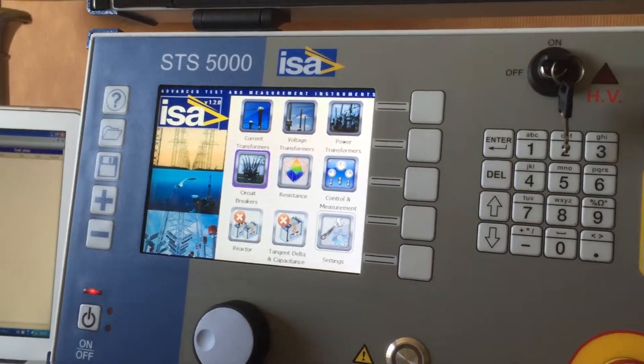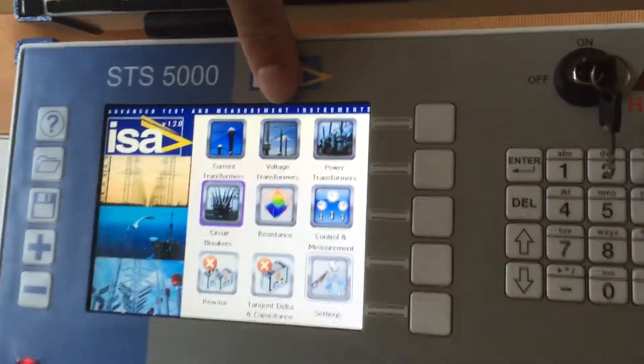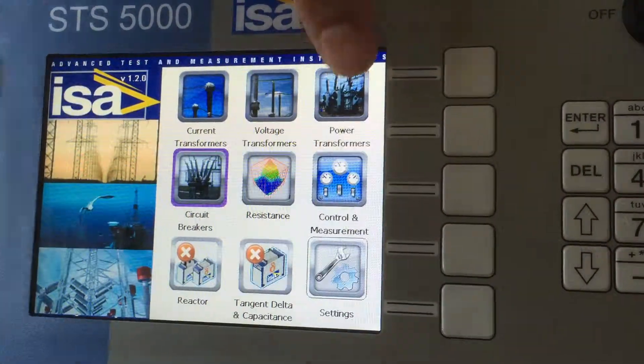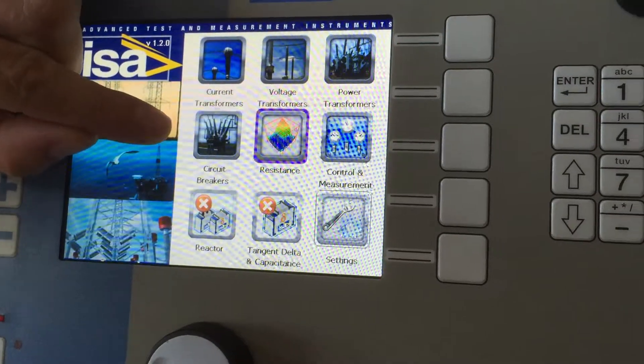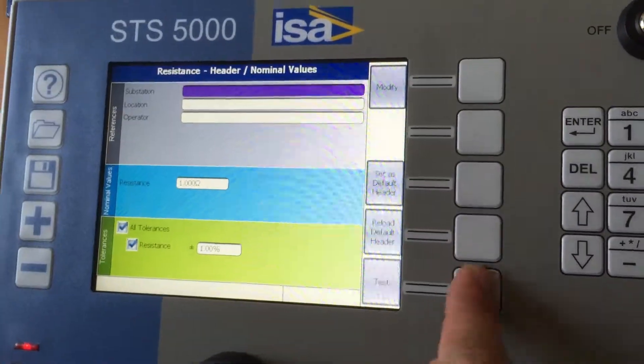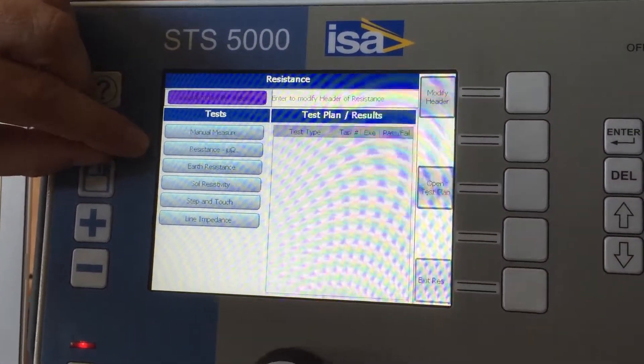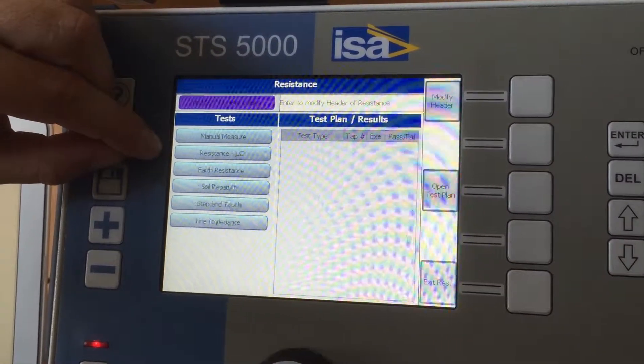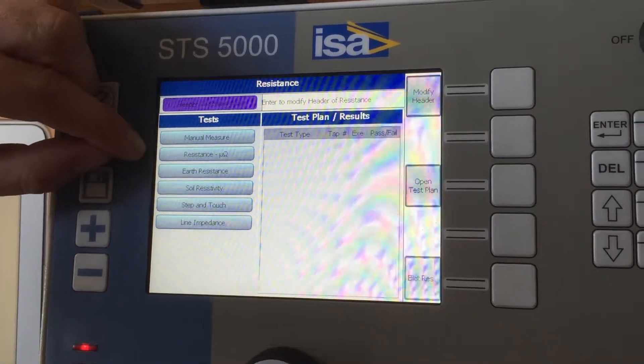Being a multifunctional test set, this test set can test current transformers, voltage transformers, and power transformers. It also covers some features of circuit breakers and resistance — you can simply measure the contact resistance of your circuit breaker, or not only a circuit breaker but the bus bar, up to 0.5 microohms.